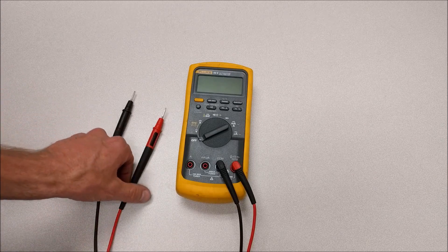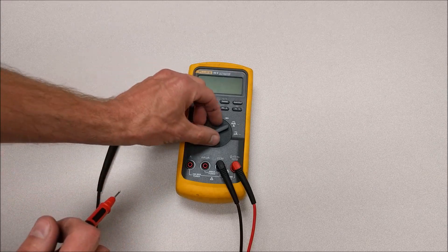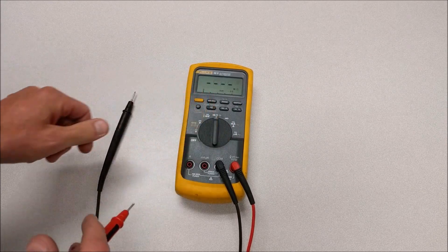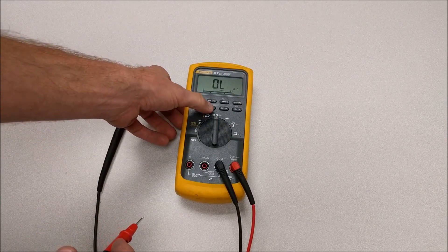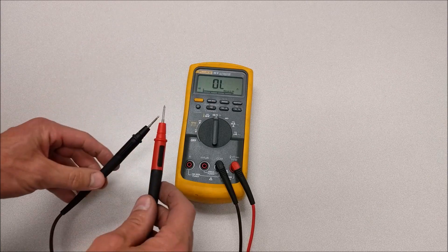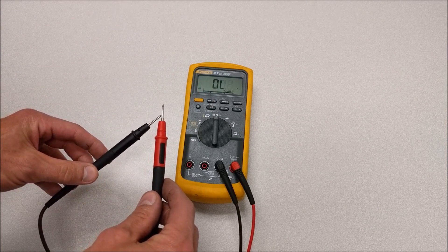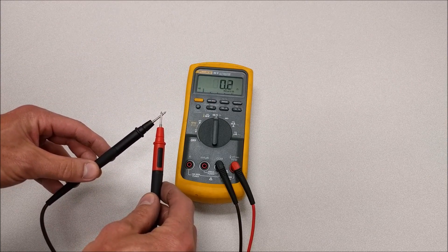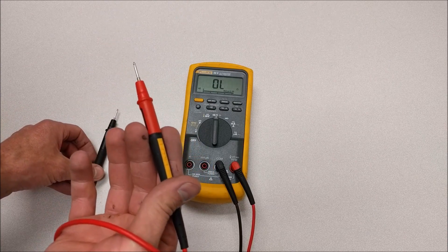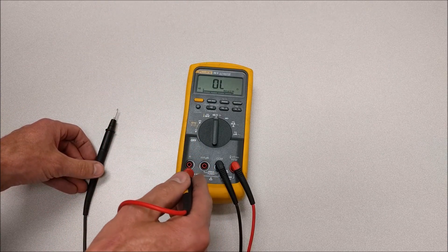And those fuses can blow, but there's a quick way to check those, and that's to turn the multimeter to the ohm setting. If you've got an audible continuity checker, you can also hit that button so that it beeps when you have continuity or low resistance.